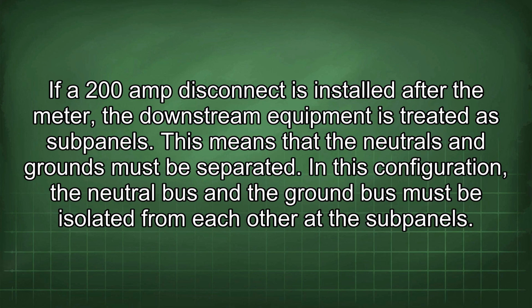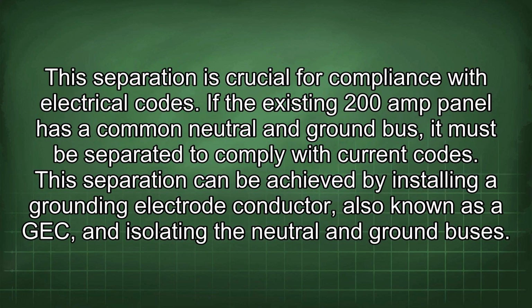If a 200 amp disconnect is installed after the meter, the downstream equipment is treated as subpanels. This means that the neutrals and grounds must be separated. In this configuration, the neutral bus and the ground bus must be isolated from each other at the subpanels. This separation is crucial for compliance with the electrical codes.